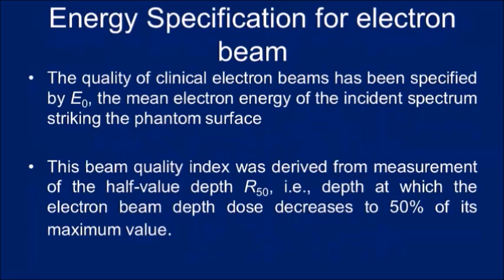For energy specification of electron beams, the nominal energy E0 is the label given to the beam (e.g., 6 MeV), but the actual measured energy may differ slightly. The beam quality index for electron beams is R50, the depth at which the electron beam depth dose is 50% of its maximum value — analogous to TPR20,10 used for photon beams.